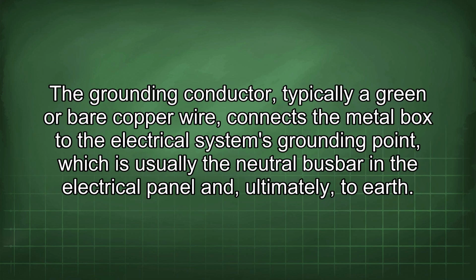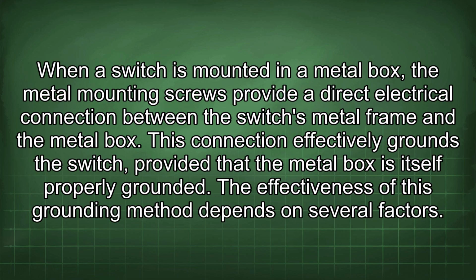The grounding conductor, typically a green or bare copper wire, connects the metal box to the electrical system's grounding point, which is usually the neutral busbar in the electrical panel and, ultimately, to earth. When a switch is mounted in a metal box, the metal mounting screws provide a direct electrical connection between the switch's metal frame and the metal box. This connection effectively grounds the switch, provided that the metal box is itself properly grounded.